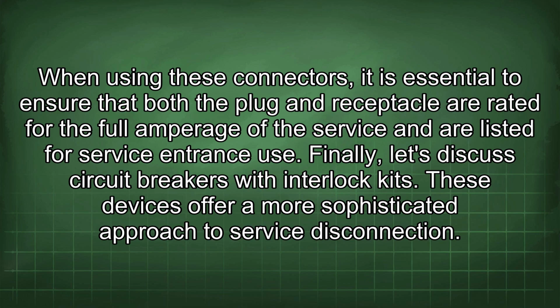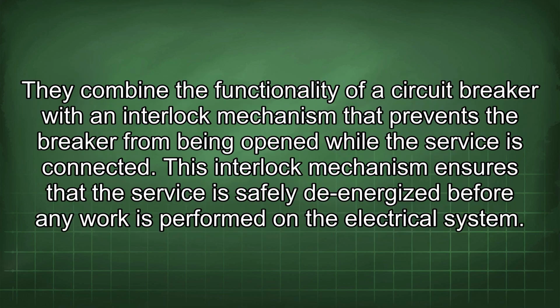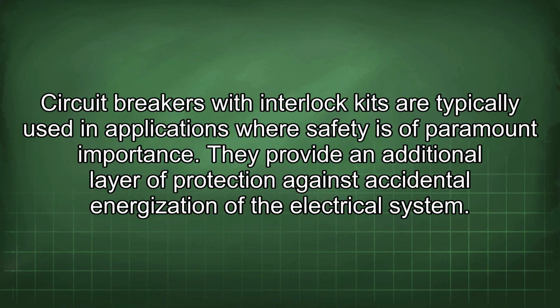Finally, let's discuss circuit breakers with interlock kits. These devices offer a more sophisticated approach to service disconnection. They combine the functionality of a circuit breaker with an interlock mechanism that prevents the breaker from being opened while the service is connected. This interlock mechanism ensures that the service is safely de-energized before any work is performed on the electrical system. Circuit breakers with interlock kits are typically used in applications where safety is of paramount importance. They provide an additional layer of protection against accidental energization of the electrical system.